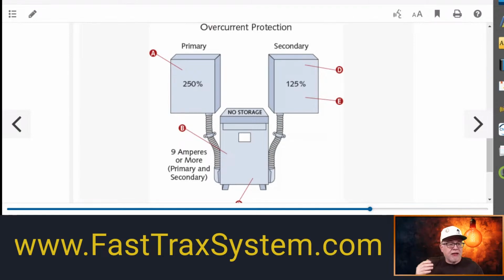So there is a possibility, and the code allows me to go up if I've got primary and secondary protection. An example of that is in this panel here. If these secondary conductors are terminating into an overcurrent protected device, let's say under the 10-foot rule, then they're not only protecting this panel board, but we also know that we're not allowed to use the next size up rule for these secondary conductors. So they will be sized equal to or greater than the overcurrent device that they terminate into. Okay. So in this scenario right here, everything is okay. Everything will be protected in that scenario. But you could have a transformer feed actual multiple loads. You want to keep that in mind.